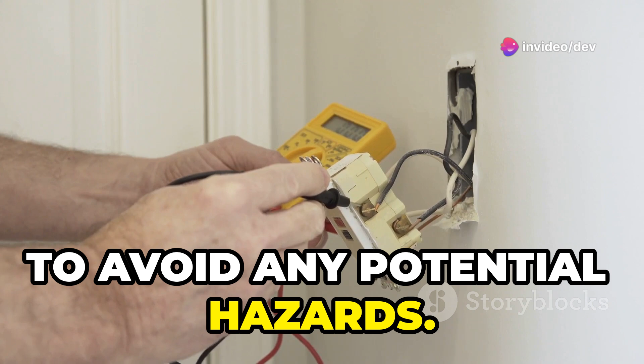If there's no light, beep, or vibration, it indicates that the tester has not detected any voltage. The circuit should be dead. However, always proceed with caution and never assume the circuit is completely safe without further verification. Always double-check to be sure. It's a good practice to test multiple times to confirm the absence of voltage, ensuring your safety before proceeding with any electrical work.